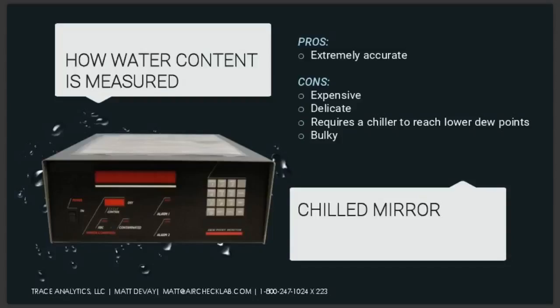But they've got a lot of those same drawbacks as electrochemicals. They take a long time to equilibrate. So you hook it up and it's probably going to be a good 30 or 40 minutes before you'll get a stable reading, particularly for lower dew points. They have a lot of parts that have to be properly aligned for it to work, so they don't really tolerate being moved around or bumped that much. They tend to mostly live in labs on a shelf where they don't have to move around. So that makes them kind of delicate instruments. And then bulky, obviously, and if you're trying to reach lower dew points, typically you need a second chiller unit to get that mirror down to colder temperatures, and that's an even bigger and bulkier piece of equipment than the dew point hygrometer itself.